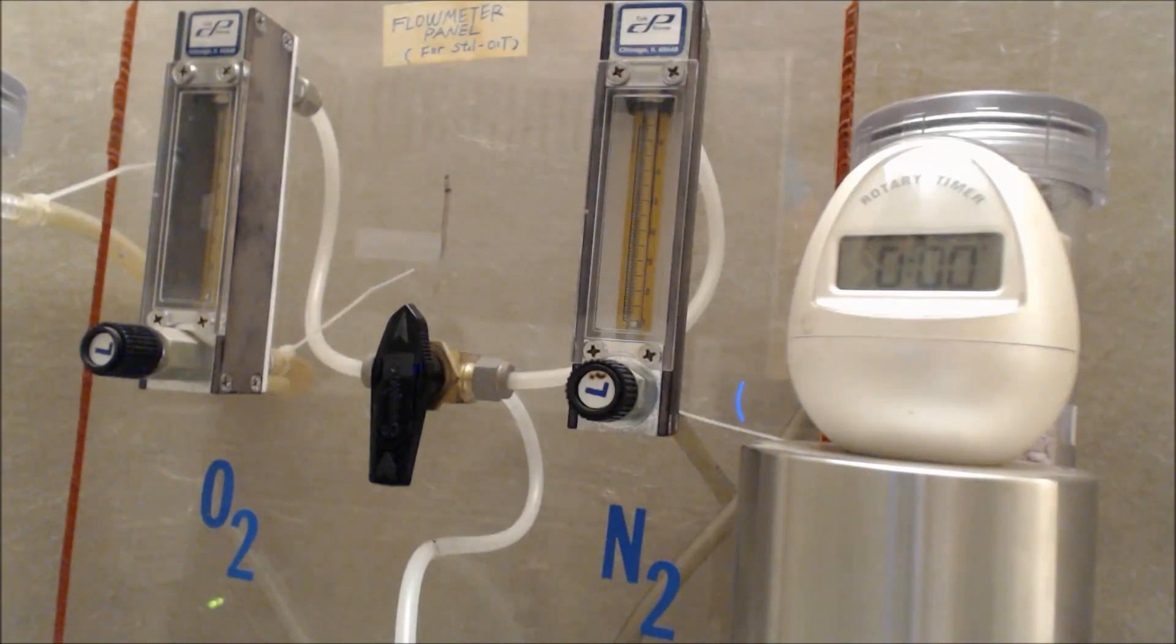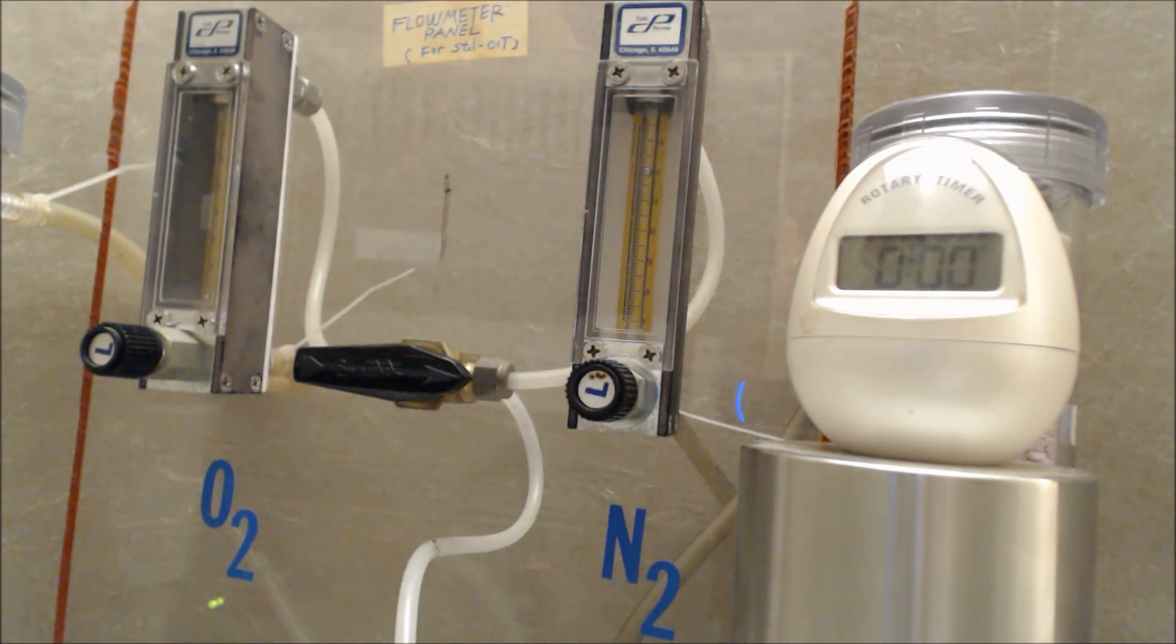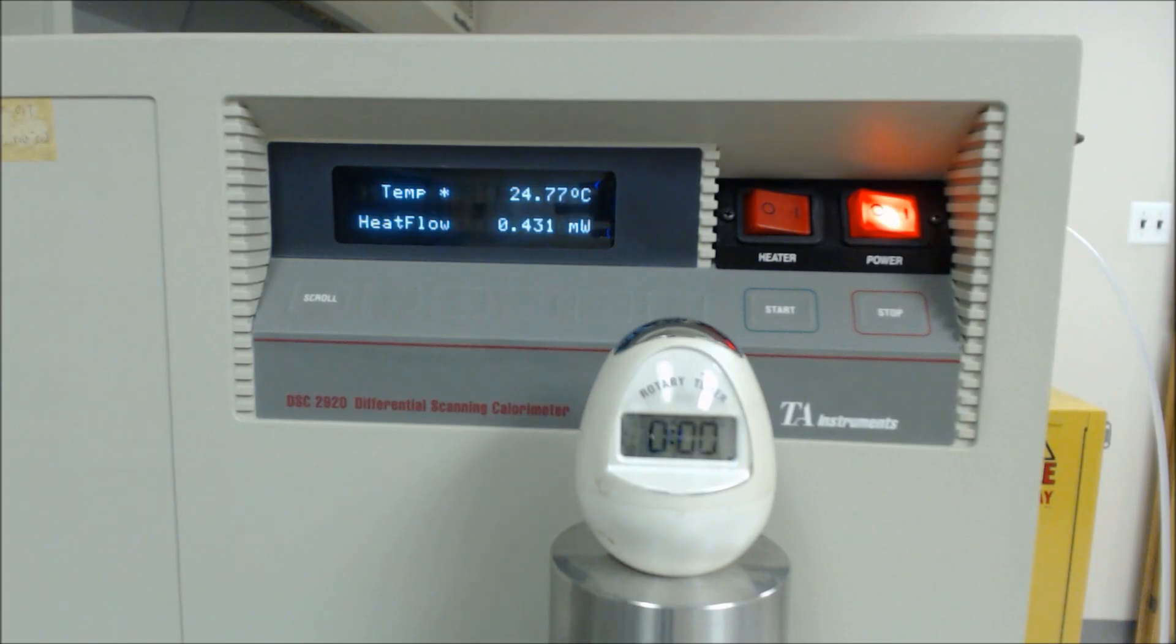At this point in our standard OIT test it's time to introduce gas into the cell. We will use this flow meter panel to introduce 5 psi or 34 kilopascals of nitrogen gas at a flow rate of 50 milliliters per minute. One important thing to note is that you must wait several minutes after turning on this nitrogen gas in order to let any oxygen be purged from the cell. After waiting several minutes, we're ready to start.